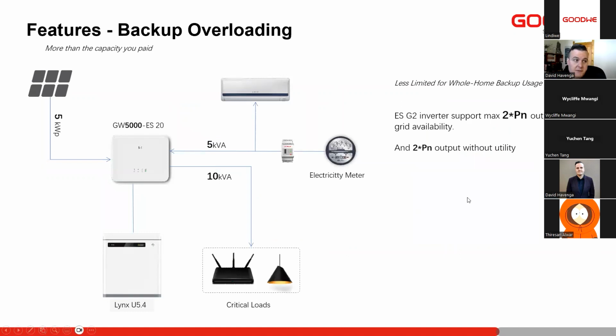Then the ESG2's backup overload. The ESG2 can backup overload up to 2 times the rating, up to a maximum of 10 kilowatts. So the 5 and the 6 kilowatt both do 10 kilowatts overload on the backup. When the grid is available, it can constantly give you 10 kilowatt output on the backup side. When we have sufficient solar and batteries available, we can also go up to the 10 kilowatts. And we will be limited to 10 seconds of overload up to 10 kilowatts if we only have batteries.